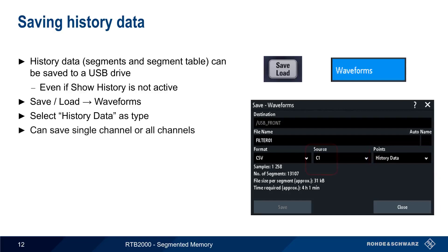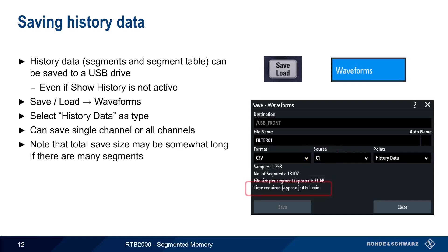History data — that is, the segments and the segment table information — can be saved to a USB drive. This is possible even if Show History is not currently active. To save history data, press the Save/Load button and then choose Waveforms. Be sure to change the data type or points to History data. Note that the segment data can be saved for a single channel or for all channels. If the number of segments is very large, the time required to save them can be somewhat long.